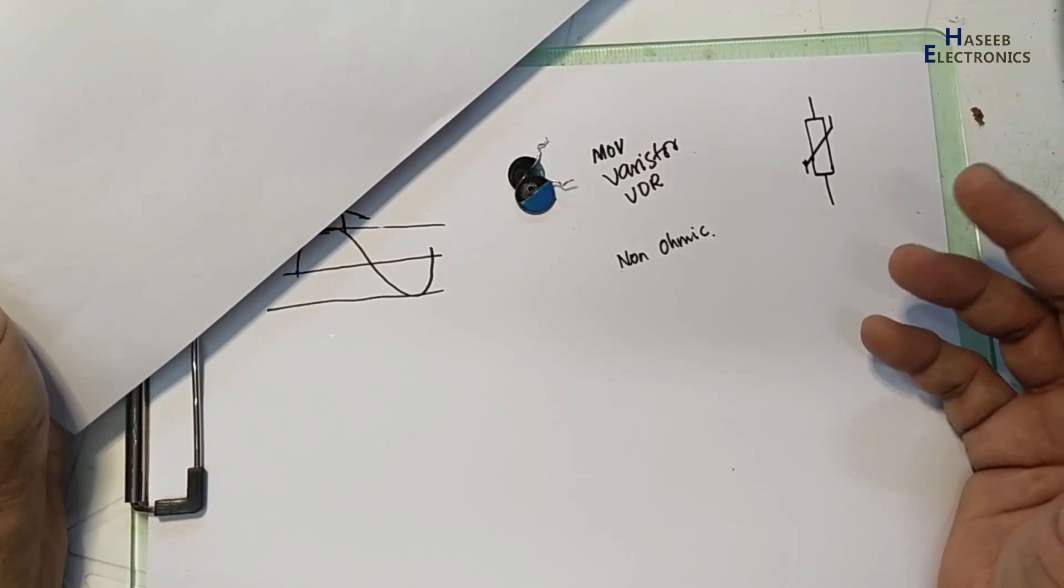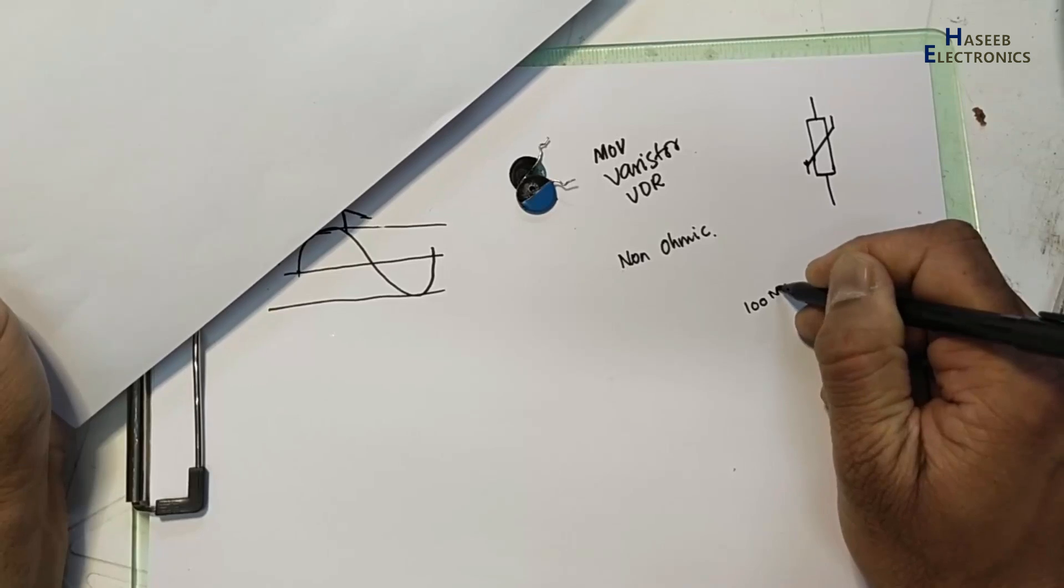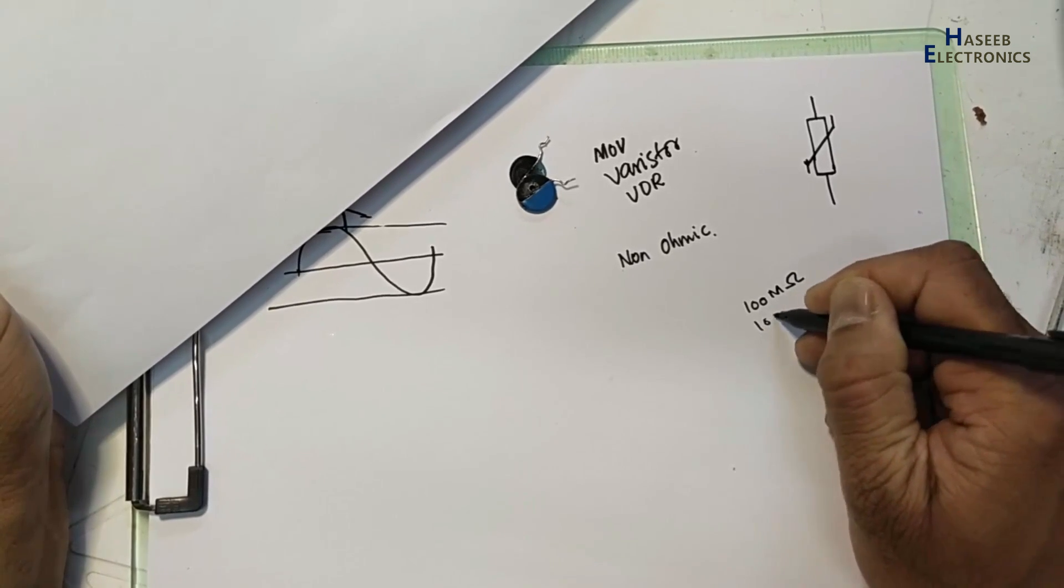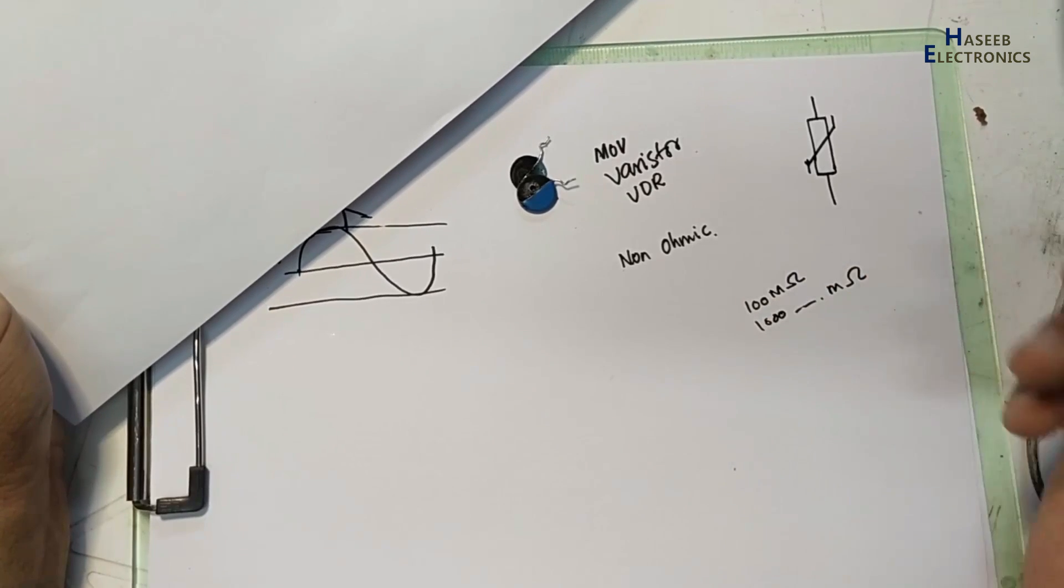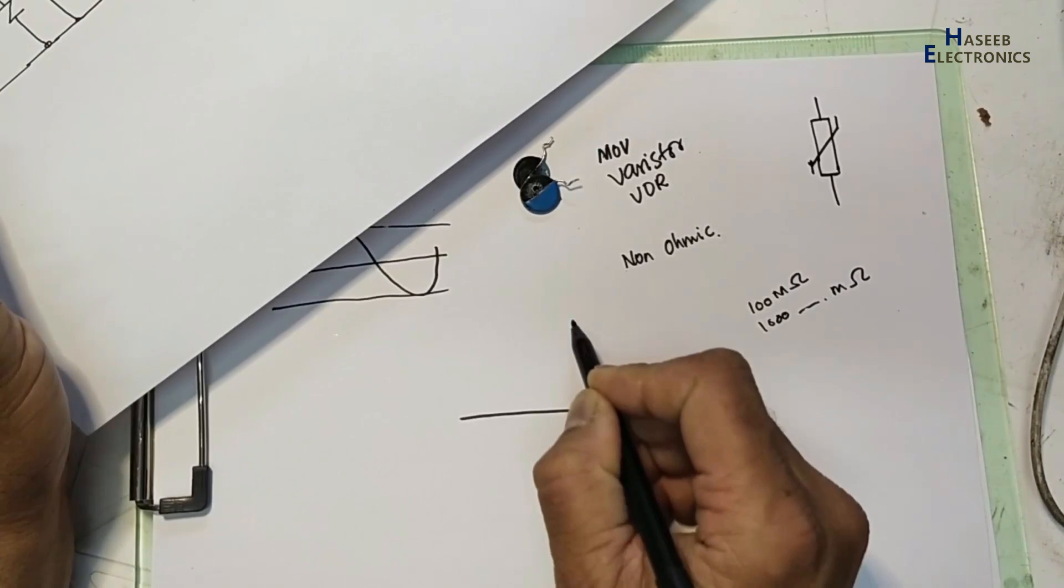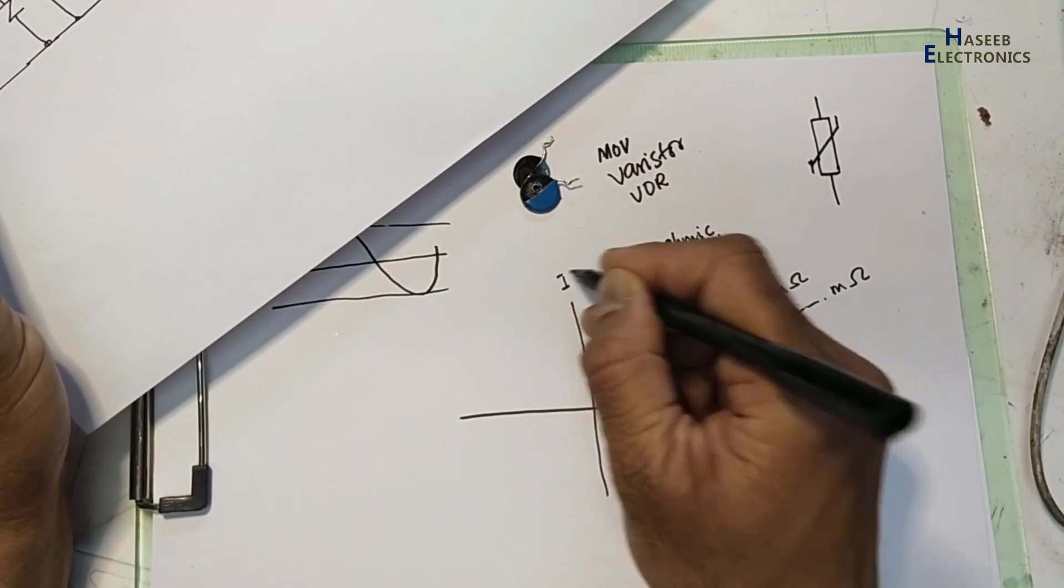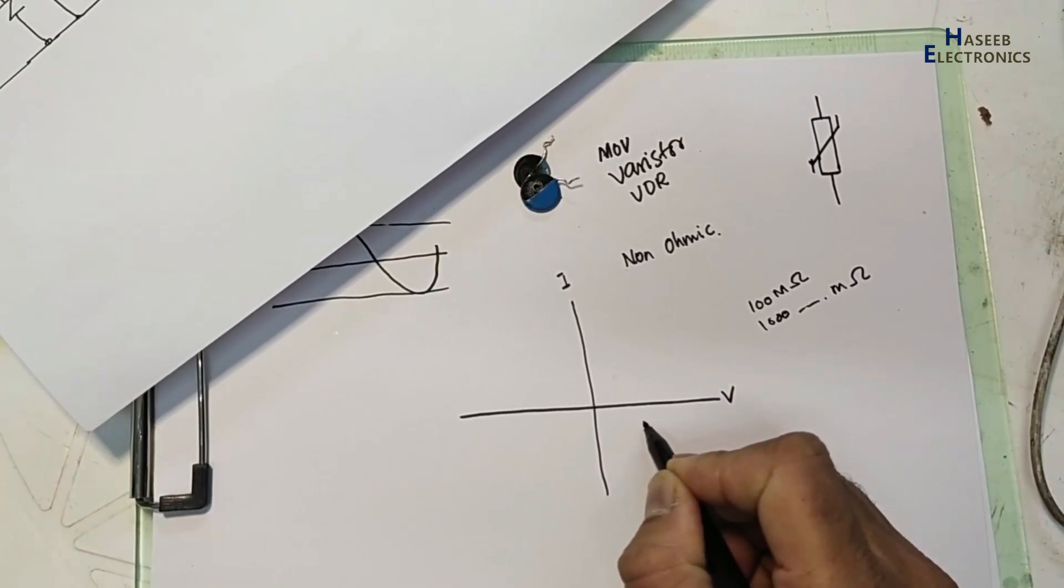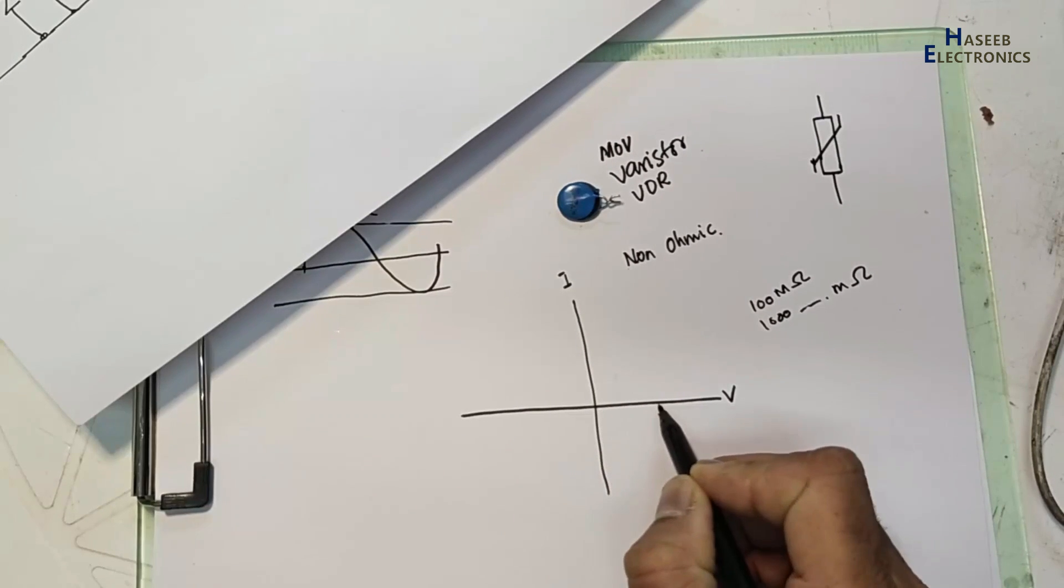Because it is connected in parallel line immediately after the fuse - line and neutral - when the voltages are within safe limits, its internal resistance is infinity, or we can say from 100 megaohm to 1000 megaohm. It works as an open circuit, that is non-conductive state.